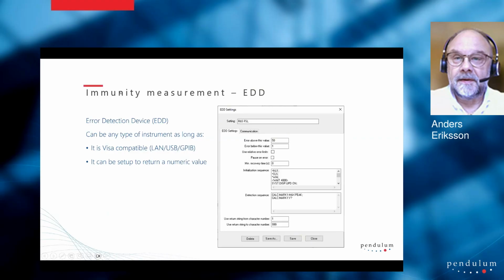The EDD can be any instrument. It needs to be VISA compatible. We need to be able to talk to it, and you need to actually provide one SCPI command. In this detection sequence, we need one command, one question, and this question needs to be answered with a number, and this number is then compared with this mask, and this is how we find out if the test object is failing or not.